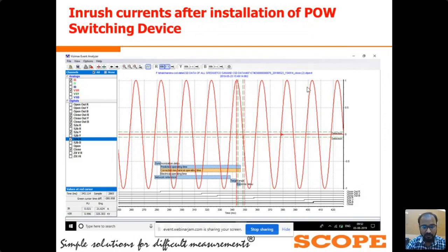You can see here how the control switching operation executed. This is the synchronization delay bar graph that is generated here. At the starting of this synchronization delay, the CSD received the command, and after calculating all the pre-calculation, the CSD executed the command near to this predicted breaker operating time. So the graph is generated here, and near to this point the breaker is getting closed.